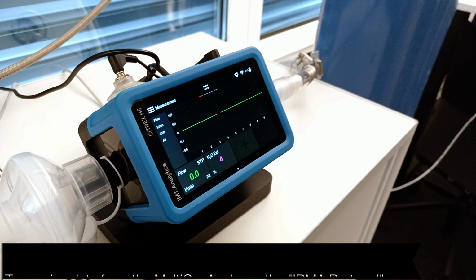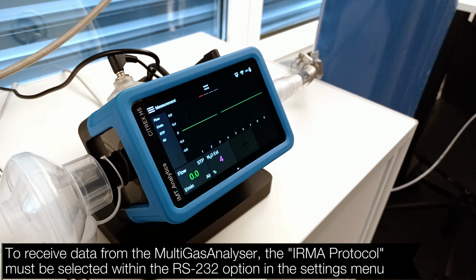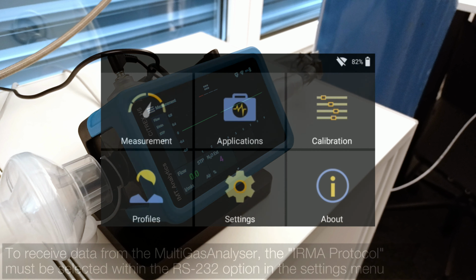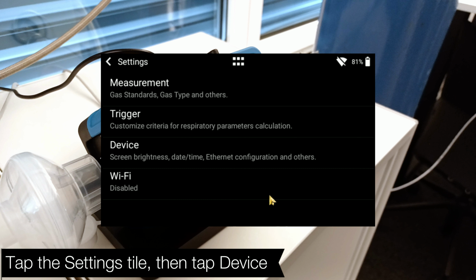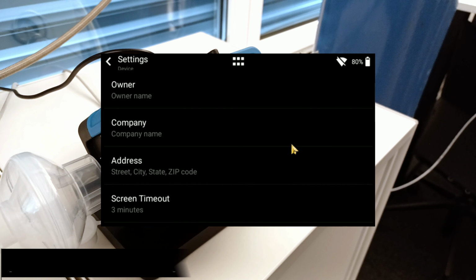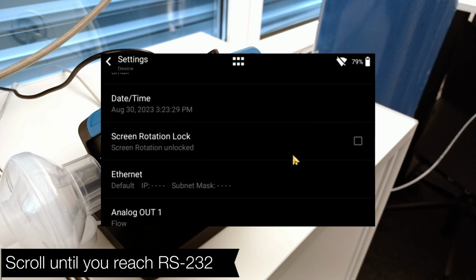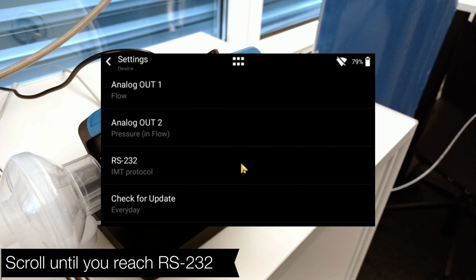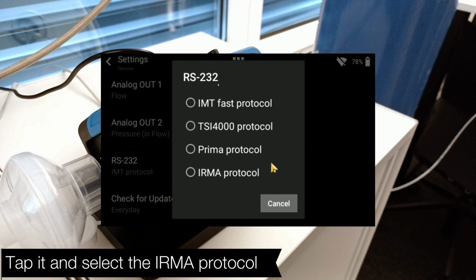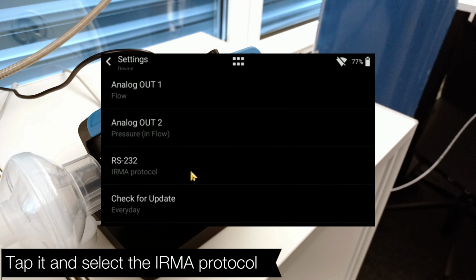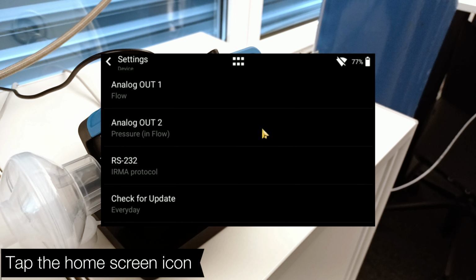To receive data from the MultiGasAnalyser, the IRMA protocol must be selected within the RS-232 option in the Settings menu. Tap the Settings tile, then tap Device. Scroll until you reach RS-232. Tap it and select the IRMA protocol. Tap the home screen icon.